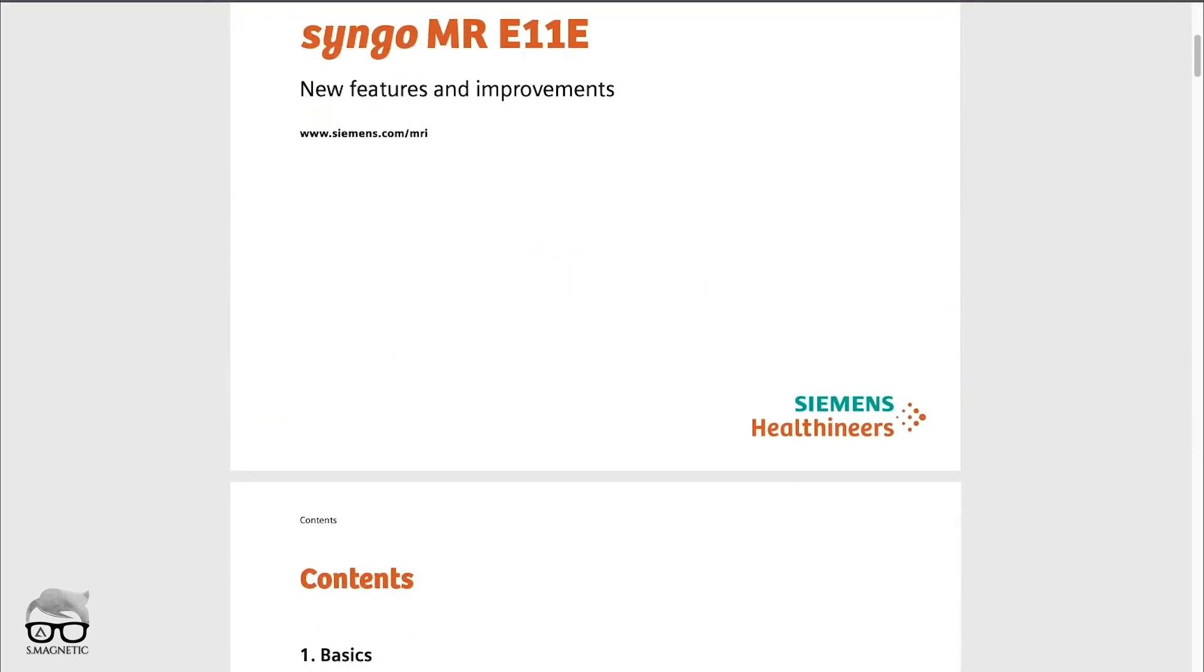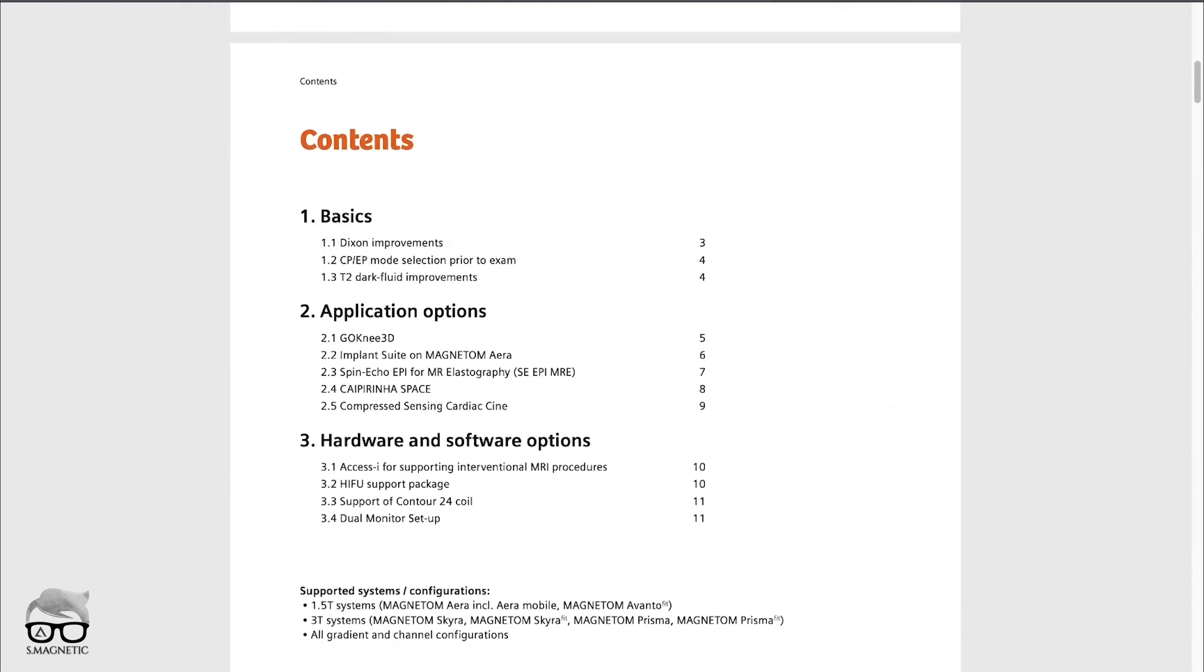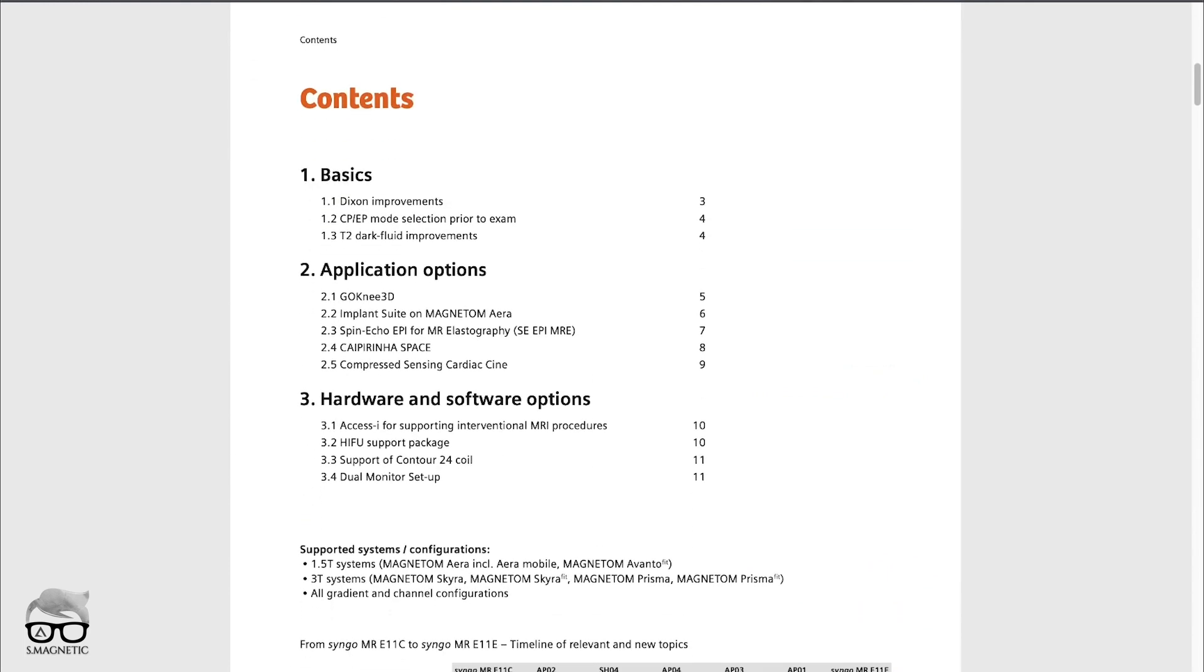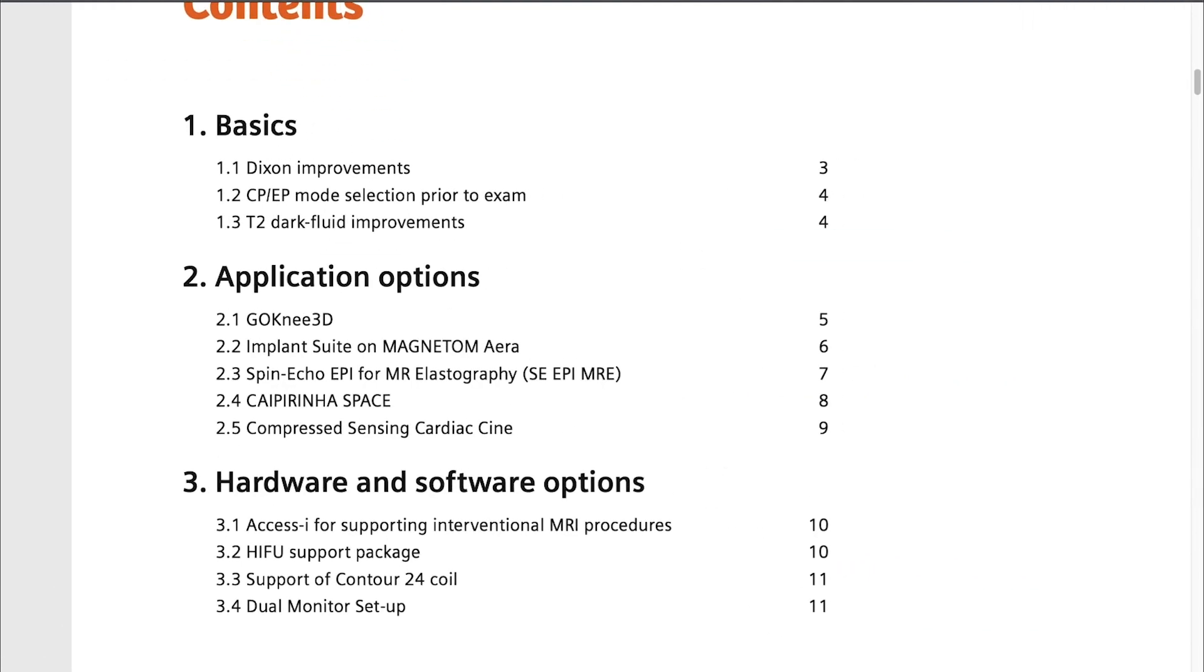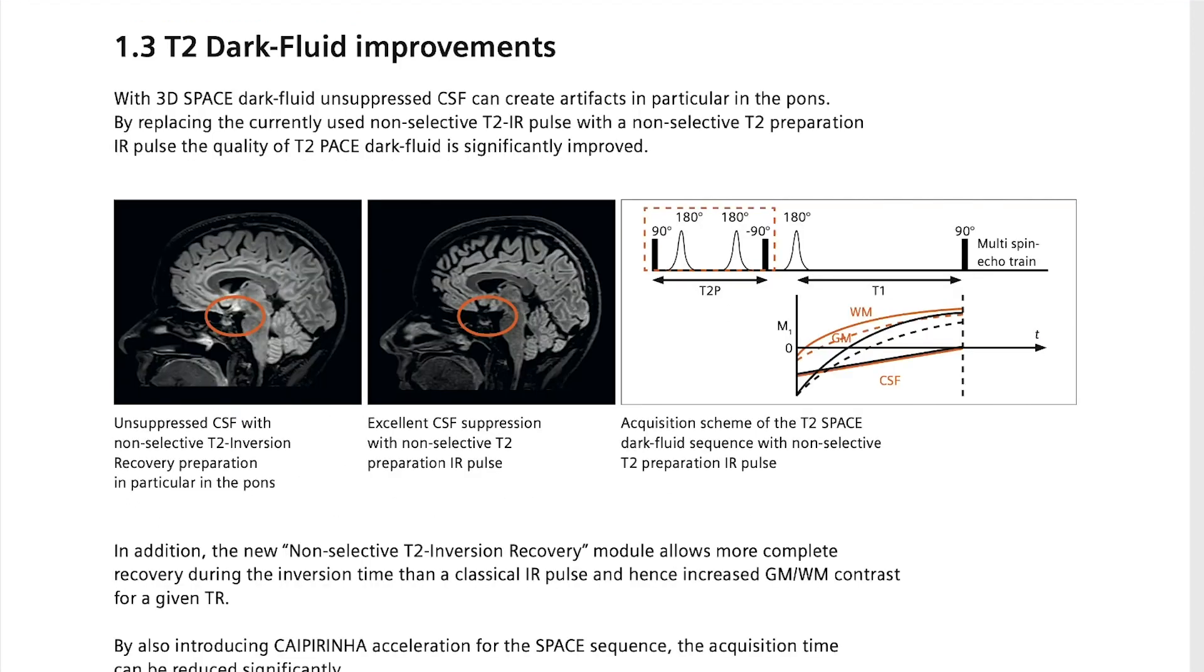If you look into the details list of the upgrade to E11E, there's a lot of improvements going on, but especially one thing that makes me curious: the 3D FLAIR improvement. Over the years we know that in the pons area, whenever you're doing 3D FLAIR, there can be some flow artifacts which can cause trouble, especially on 3T.